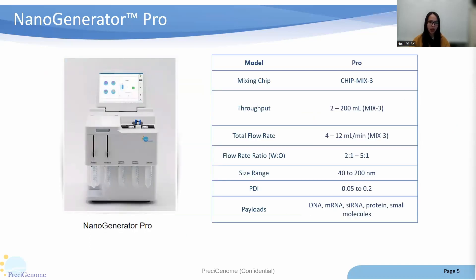Nanogenerator Pro has a throughput from 2 to 200 milliliters. This production range is suitable for discovery and early pre-clinical applications. Nanogenerator Pro is a fully integrated system. It contains two individual flow units with three standard syringe pumps, which provide precise control on total flow rate and flow rate ratio.